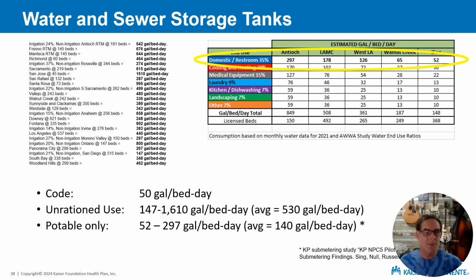Now, to contrast the oversizing that we're doing on our fuel tanks, we can talk about the water tanks. The code requires us to size our water tanks for 72 hours based on 50 gallons per bed per day. I've tried to find where that number came from, and nobody knows. Just nobody knows. What we do know is that our unrationed water use varies between 147 and 1,600 gallons per day. The average at our sites is 530 gallons per bed per day, but you would never use the average because the variance is so wild.